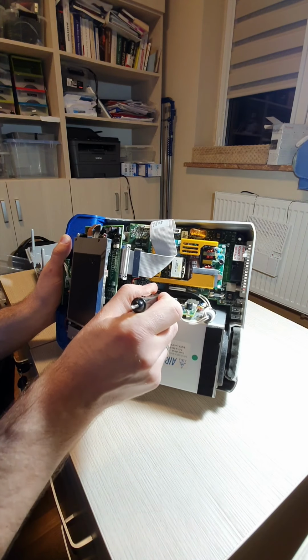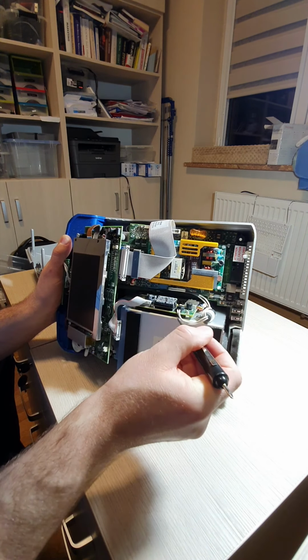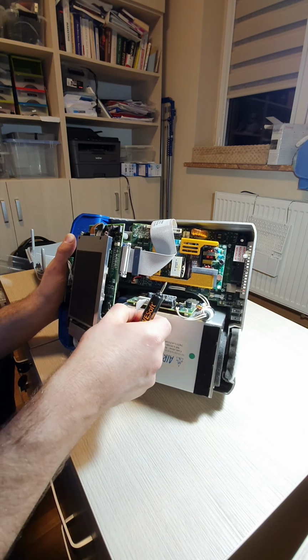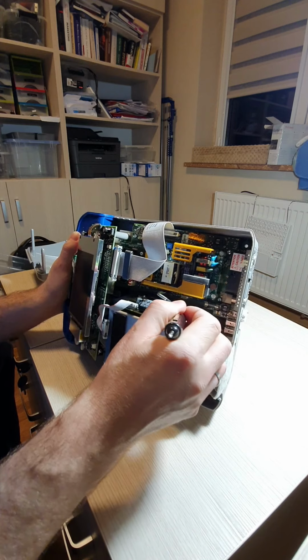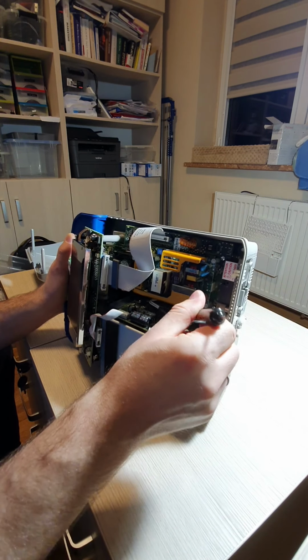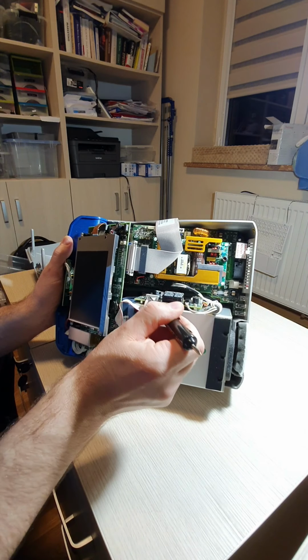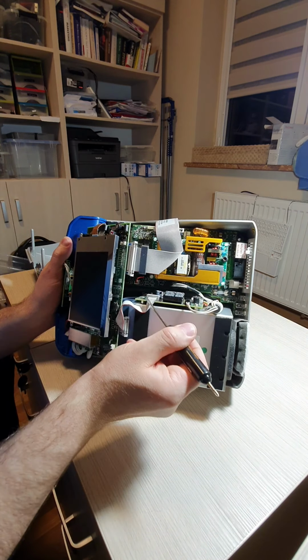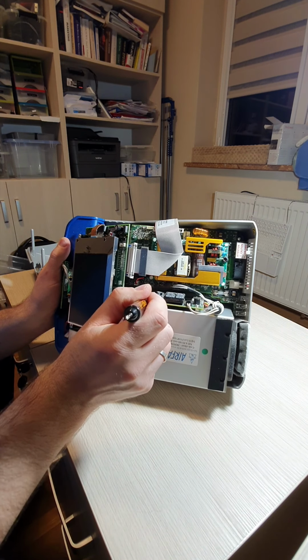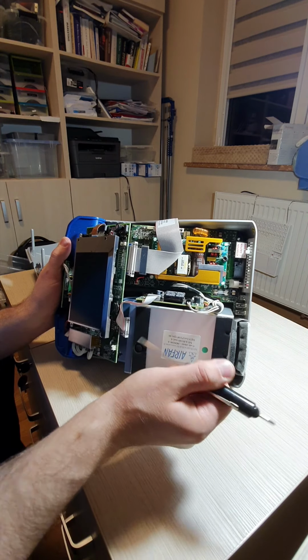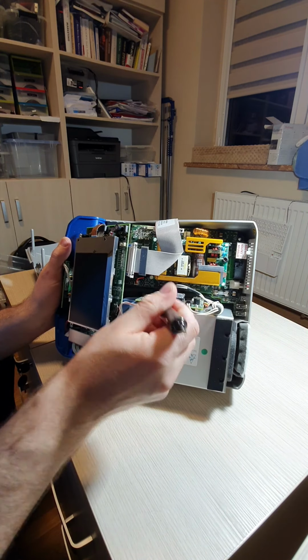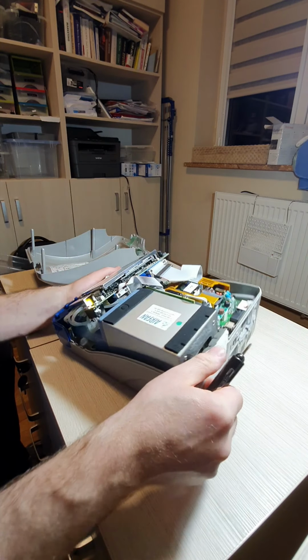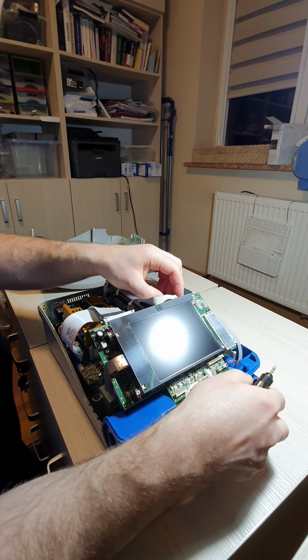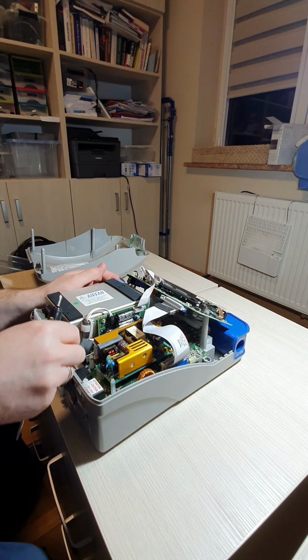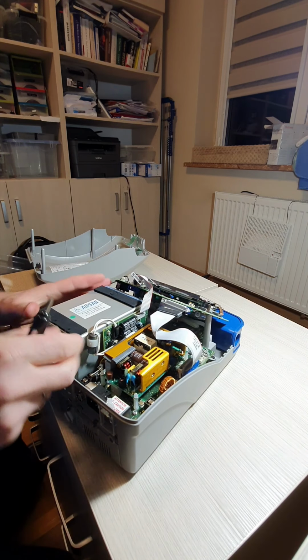Essentially what you do, you need to deliver DC voltage, which controls the speed, from the power supply, which is this plug, and simply connect Hall sensors and windings and the temperature sensor, which go here. Here on this connector is the speed signal, which is DC voltage, and the feedback signal, which is pulses, and the main processor simply adjusts the voltage to get the correct RPM. This turbine is produced by the Airfan company, a French company specialized in this type of equipment for medical purposes. So let's take it outside if it's possible.